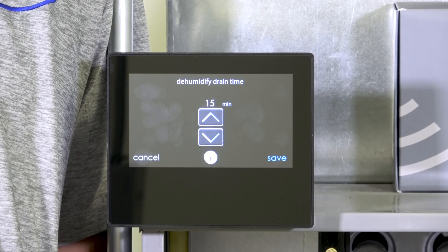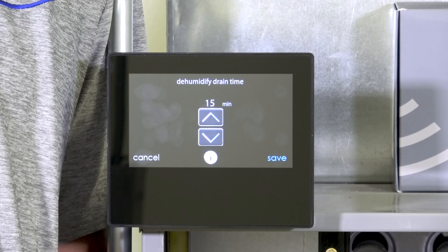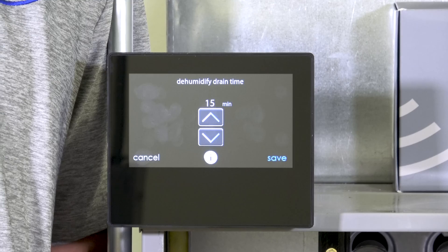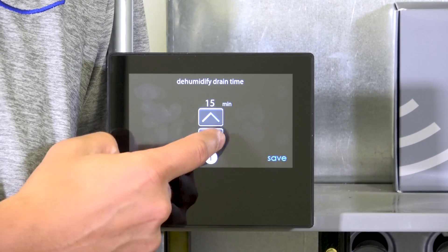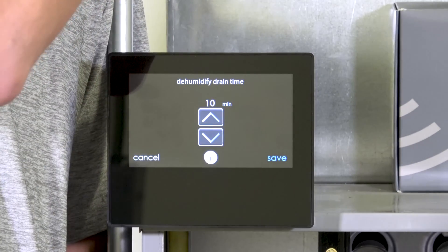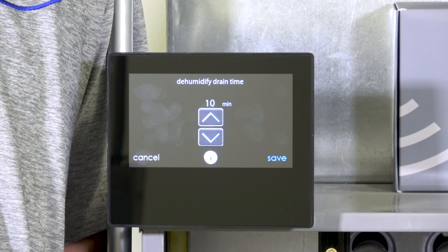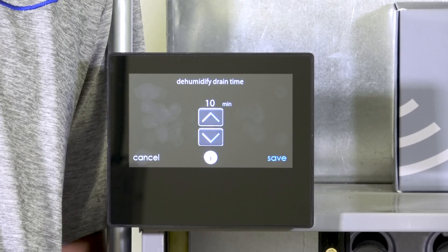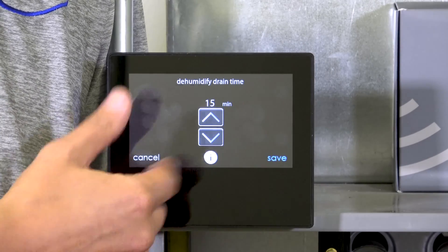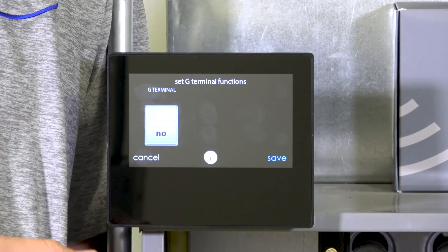Dehumidification drain defaults to 15 minutes. After a cooling or dehumidification call ends and the compressor shuts off, we also turn off the main blower — even if the consumer has set it to run continuous fan 24/7 — for a default of 15 minutes, though you can set it to 10. This allows time for water to drain down the evaporator coil into the condensate pan. If you run the blower immediately, it blows moisture off the coil back into the airstream, defeating the dehumidification. I usually set it to 10; 15 is fine for more humid climates like Florida.